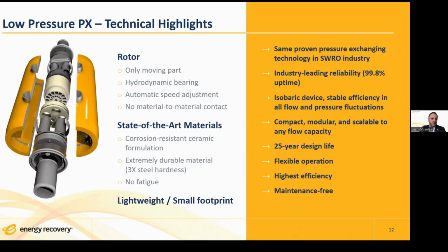It is manufactured of ceramic components, so it is completely corrosion-free. It is also very durable. It is 3 times harder than steel, and it suffers no fatigue. It is also lightweight and has a small footprint. Also, in terms of design, it is compact and modular. It means that we can design any system, no matter the size it has. We can put PX elements in parallel to achieve the required flow.